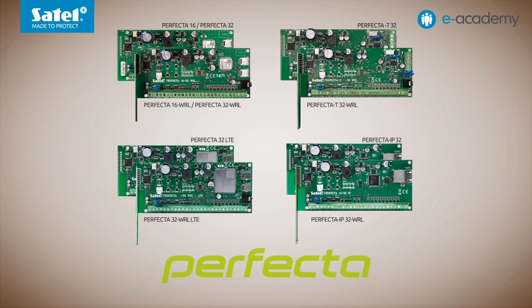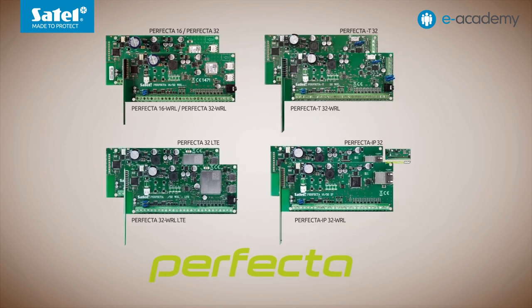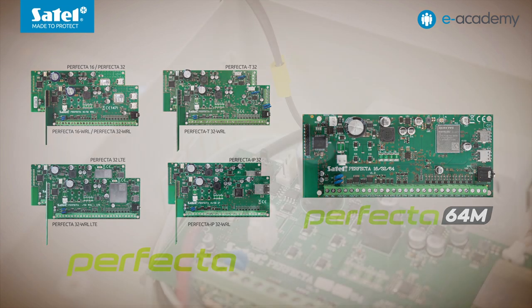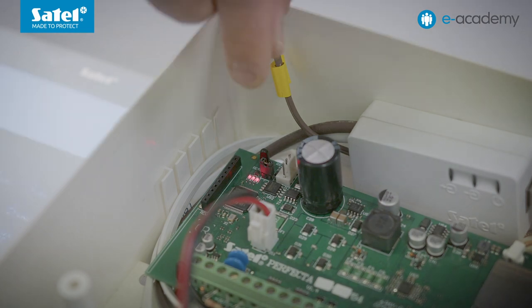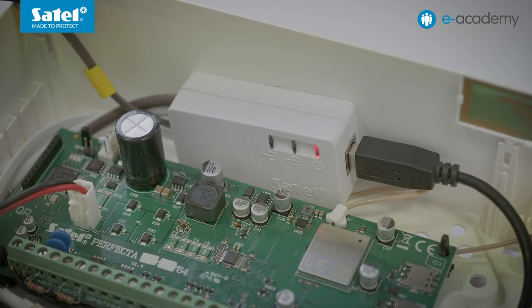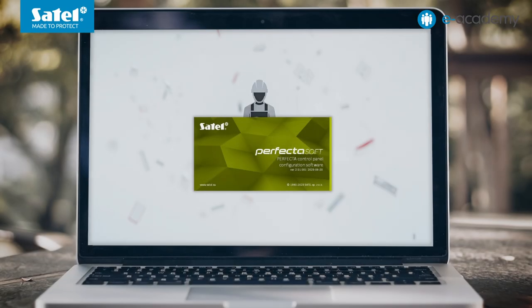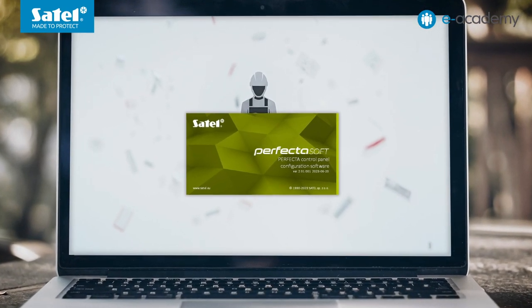Although Perfecta 64M shares many features with its sister models, it offers much more than they do. So let's focus on discussing what makes it stand out. The system we'll be using is already pre-connected. When starting up the control panel, we activate the service mode using the pins and the jumper. The connection to the computer is made via a USB RS converter connected to the RS-232 TTL port on the control panel. The PerfectaSoft program is running, communication has been established, and the identification of the connected modules was carried out. Now we will go through a number of functions and settings to highlight the differences and strengths of the presented control panel.